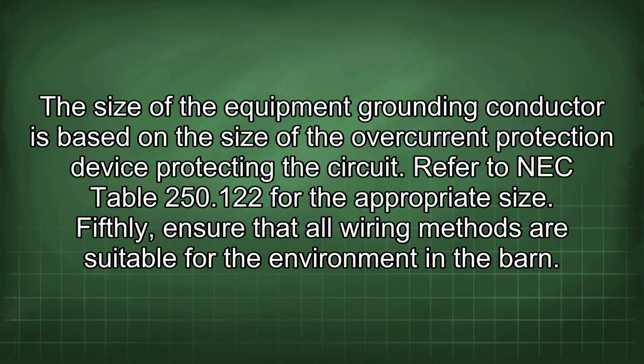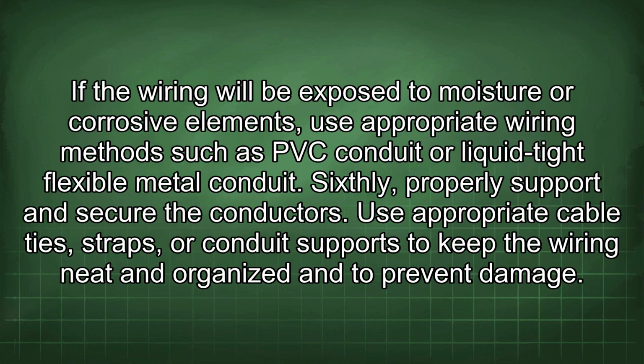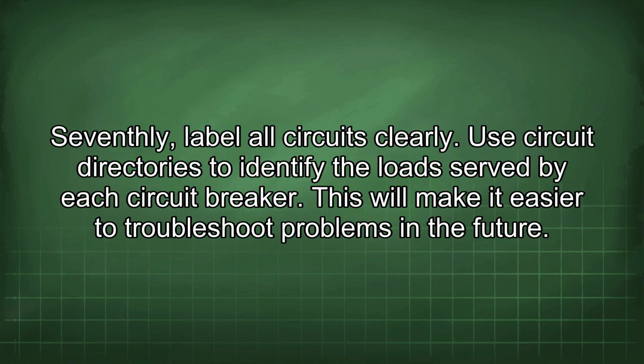Fifthly, ensure that all wiring methods are suitable for the environment in the barn. If the wiring will be exposed to moisture or corrosive elements, use appropriate wiring methods such as PVC conduit or liquid-tight flexible metal conduit. Sixthly, properly support and secure the conductors. Use appropriate cable ties, straps, or conduit supports to keep the wiring neat and organized and to prevent damage. Seventhly, label all circuits clearly. Use circuit directories to identify the load served by each circuit breaker. This will make it easier to troubleshoot problems in the future.